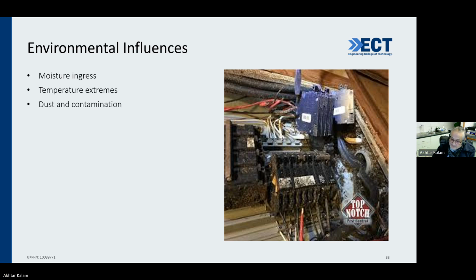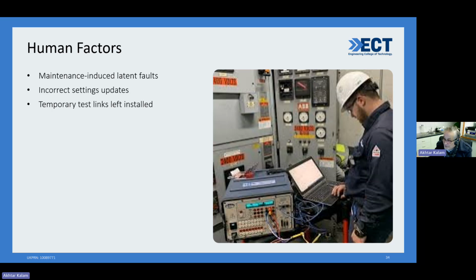Look at what is done to that machine. My friend, I told you, the majority of the problems happen because of the human being, the operators. I don't know why, including myself, I have a bad habit of poking my hands everywhere. And remember, we are talking about system. I've taken everything as system. You are also a part of the system, my friend. So that maintenance induced latent fault, even when I'm doing the maintenance, right? You're absolutely right. Human factors are very important. And incorrect settings updates, and temporary test links left installed, all that can cause a lot of problems.